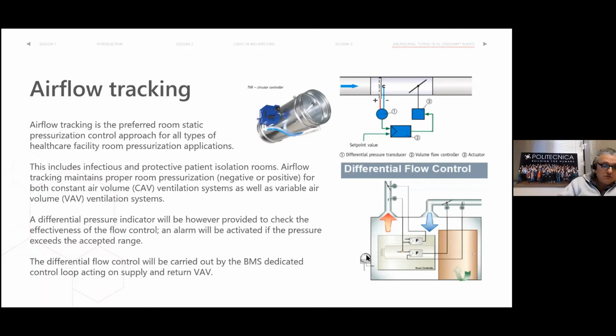And what is the most efficient system to control the pressure inside? You could test it by a differential pressure transmitter and try to control the flow rate, trying to have the right pressure inside. But as you have seen, the differential pressure value is around 5 pascals. So it is a very low value. So you would need very precise instruments, and there could be some imperfection in the adjustment that could have bad effects in the regularity of the flow. So this is not the way to do it.